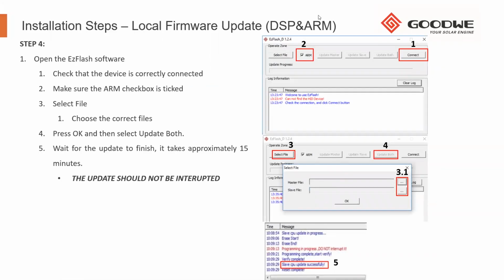But if you are going to do the local update, the EZ Flash tool is then used. This can be tricky on site if there is any electromagnetic interference, or if your computer might have some viruses and have a USB port that doesn't always work as well. It's then advisable to not do this locally and get the device connected so that we can do that remotely for you. So what the EZ Flash does is it physically erases the DSP, which is our main power controllers. And after erasing it, it then uploads the new firmware to it. So should it fail during an update, the inverter won't be in a usable state until the update has succeeded.